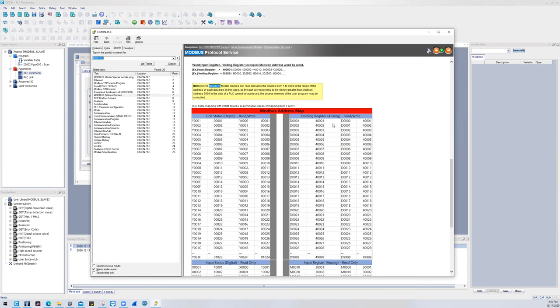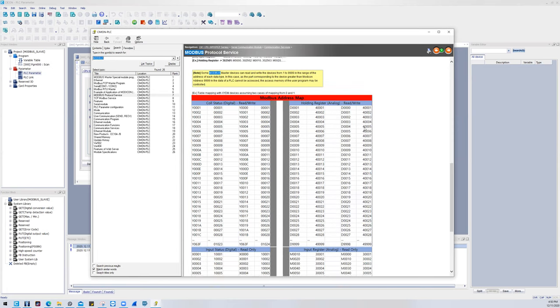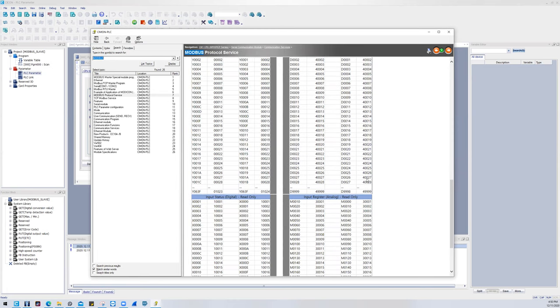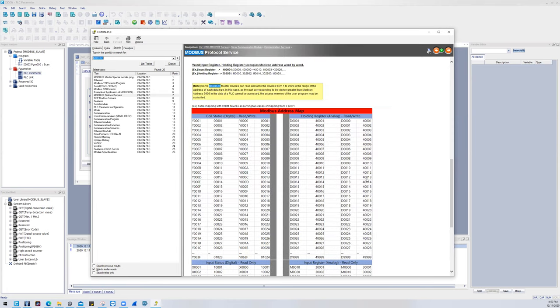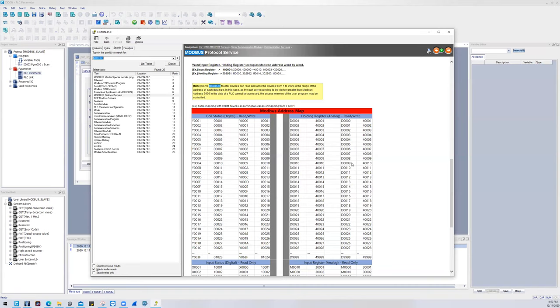Now when you jump into the 40s and 30s, it's a little bit more of a direct association. So it's a little bit easier when you're doing the addressing. So Ds literally just map one to one, but with an offset of one. So D00 maps to 40,001 and then so forth all the way down to the max. So it's just an offset of one for each register.